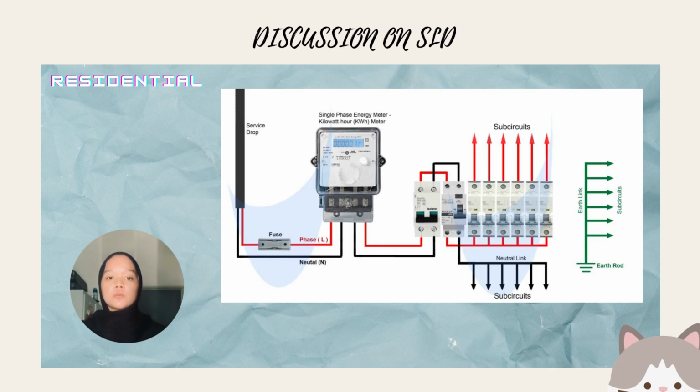My role is to briefly explain about the distribution board in residential areas. A distribution board, also known as an electric panel, is a component of an electricity supply system that divides an electrical power feed into subsidiary circuits. The electrical power supply comes from the network to the building through the main feeding cable. The cable is connected to the distribution board and the power is distributed through the breakers in the secondary circuit, which is lights and plugs.